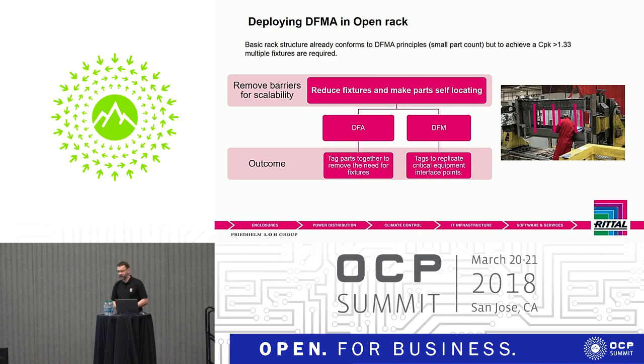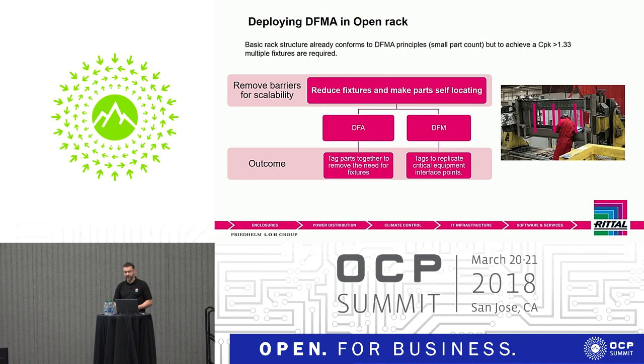How do we deploy DFMA to an open rack? The open rack design already conforms to many DFMA principles — four vertical members, top and bottom base tray; the vertical members perform many functions beyond just being structure, with all equipment piercings, forms and lances for cabling included. But how do we remove barriers for scalability and look at it again with fresh eyes? We focused on reducing fixtures and making parts self-locating.